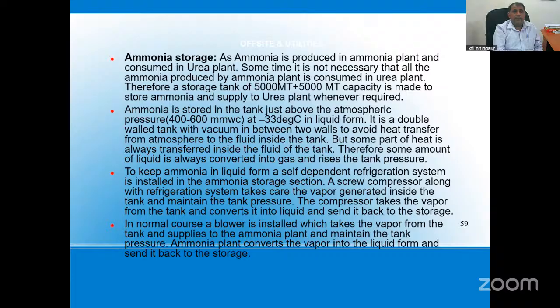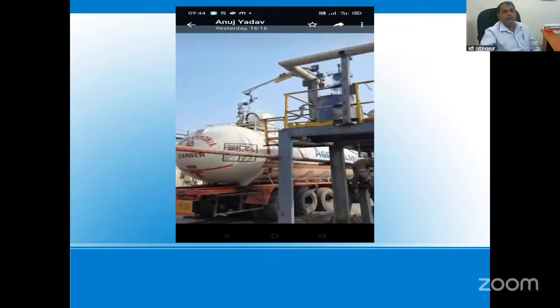This tank is not a simple tank. It is a double wall tank, and there is a vacuum between the first wall and second wall of the tank, and it is insulated on the outside. So this is also an important tank for the utility section. We also have a facility to sell the liquid ammonia to the market, and this is a very dangerous process.